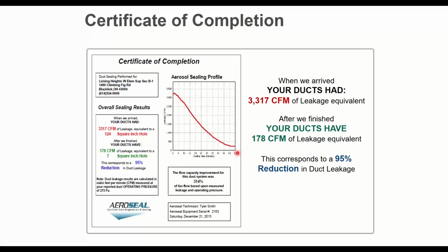It only took 50-some minutes. Someone would have been doing this there all day though, because it's going to take them a couple hours to get everything set up and close off all these registers and diffusers. And then it takes a couple hours to clean everything up. So it is an all-day project for even a system that's this small. But the actual sealing time is under an hour, which is fantastic.